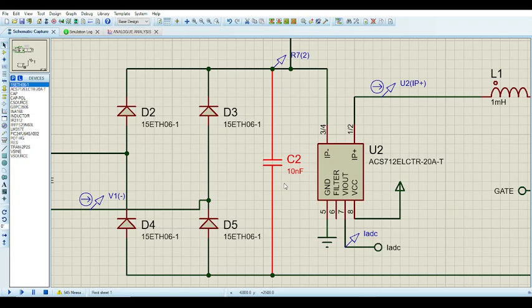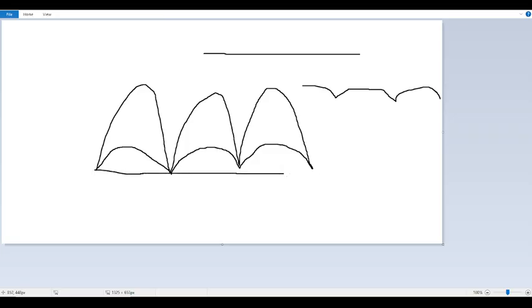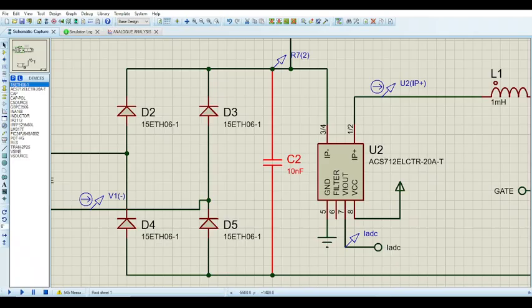Usually 1 microfarad is enough, but you should put the capacitors there and actually check that the voltage looks like this: the minimum should be as close to zero as possible. The minimum there should be zero, not 10 volts. 10 volts is not too bad, but it's better if it's at zero at those points. Maybe negative 0.5 isn't too bad either, but it should be zero. So that's the first thing to check.